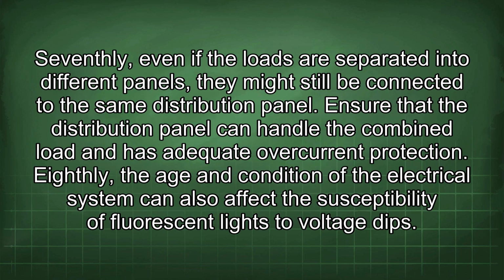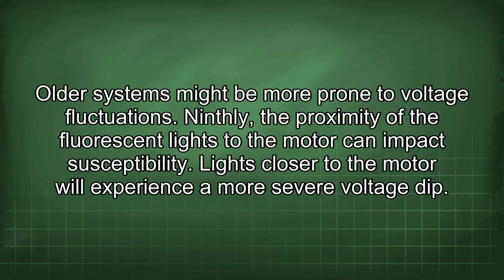Seventhly, even if the loads are separated into different panels, they might still be connected to the same distribution panel. Ensure that the distribution panel can handle the combined load and has adequate overcurrent protection. Eighthly, the age and condition of the electrical system can also affect the susceptibility of fluorescent lights to voltage dips. Older systems might be more prone to voltage fluctuations.